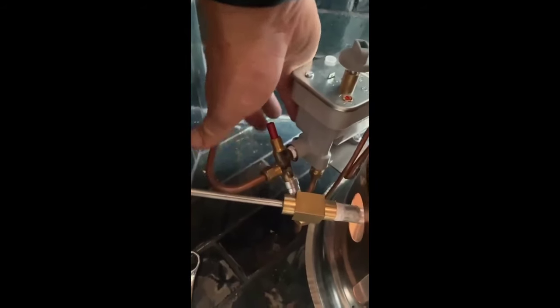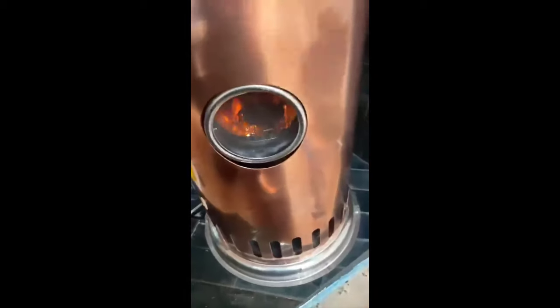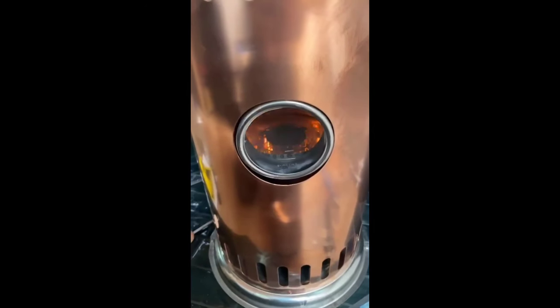We'll give it about two or three minutes — the yellow flame inside will get bigger and bigger, and once it's big enough we'll press the red button. When you push the red button down, it pushes a pin down inside the mechanism and the red part comes back up. When the thermocouple recognizes the flame, the pin will stay down until there's no flame — if it blows out or you turn it off, it recognizes that, drops the pin, and shuts the fuel off. It's not quite there yet — give it a couple more minutes and I'll come back to you.